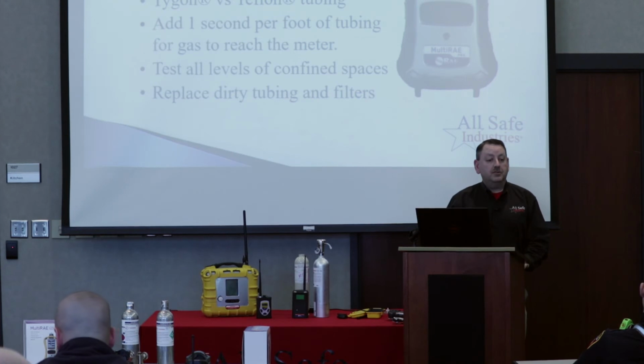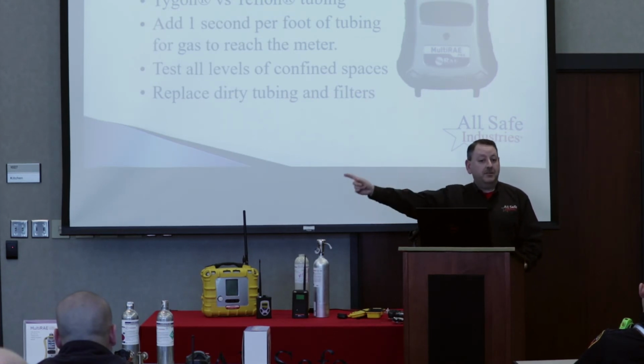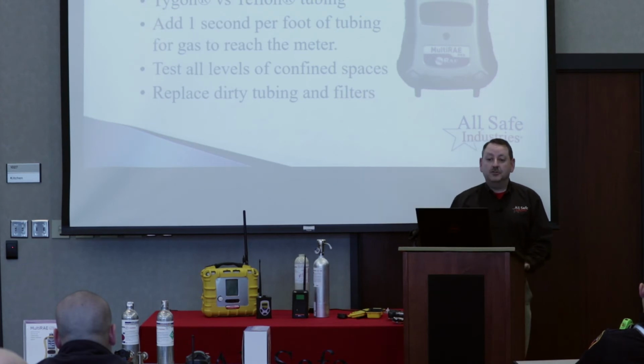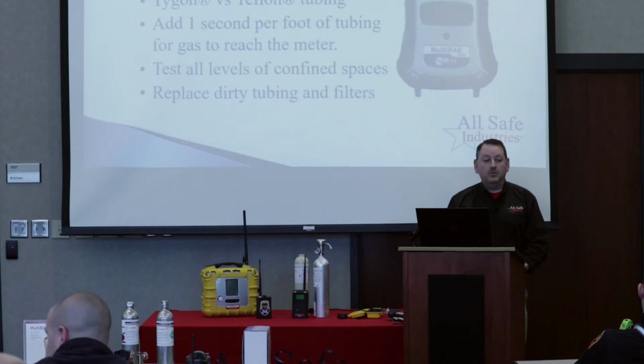Just remember, just like a fire hose, it takes a little time for the water off the hydrant to come out of the other end of the fire hose. The same is true for your sample tubing. If you're drawing through 100 foot of tubing, you're going to want to delay checking the readings until after 100 seconds has expired. So it's kind of easy to remember, about a second per foot of tubing.